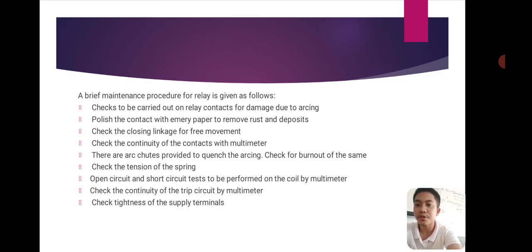Check the tension of the spring. Open circuit and short circuit tests to be performed on the coil by multimeter. Check the continuity of the trip circuit by multimeter. And last, check the tightness of the supply terminal.